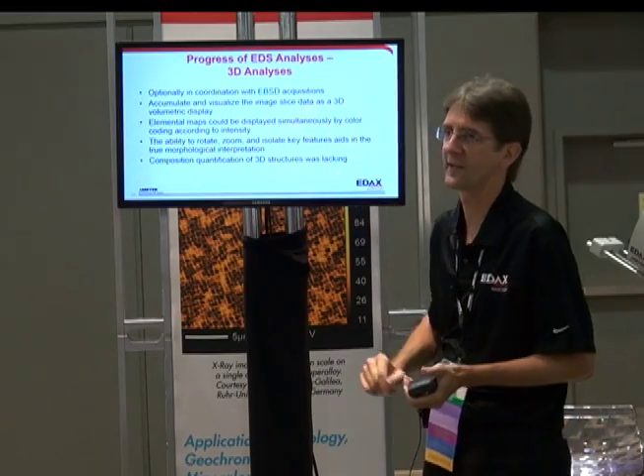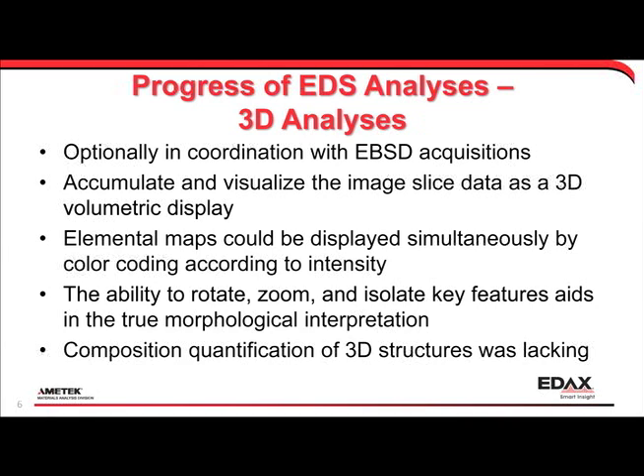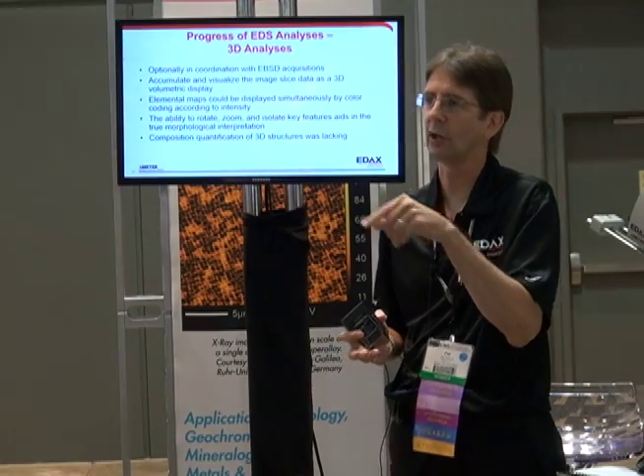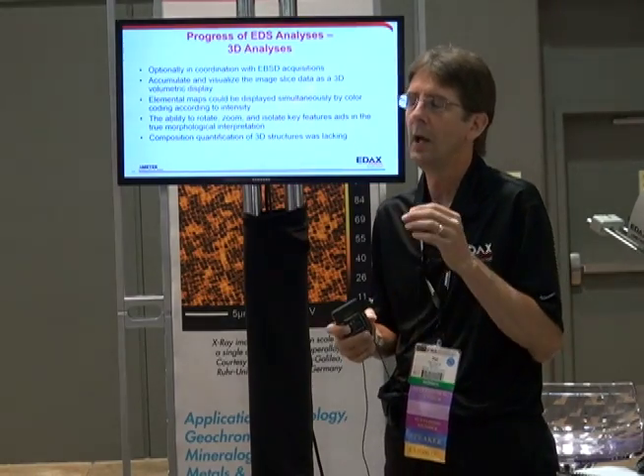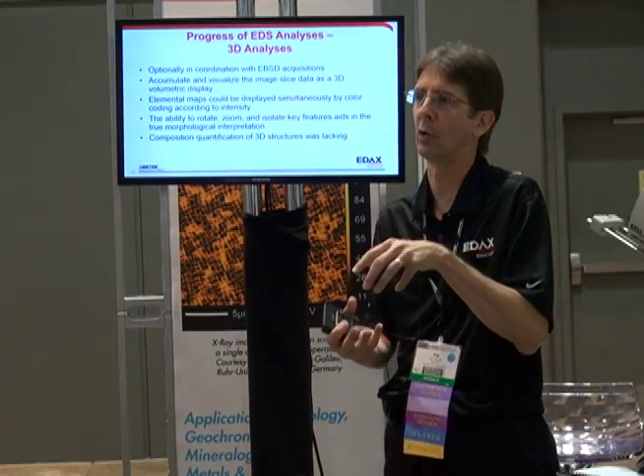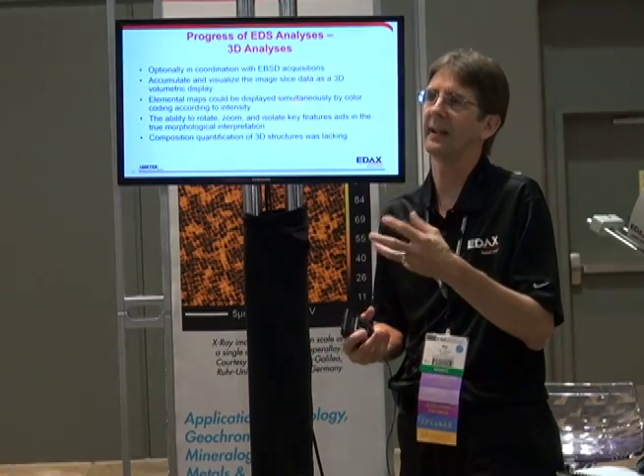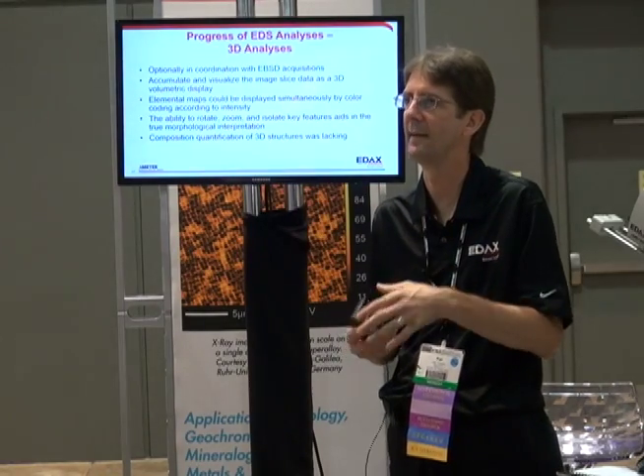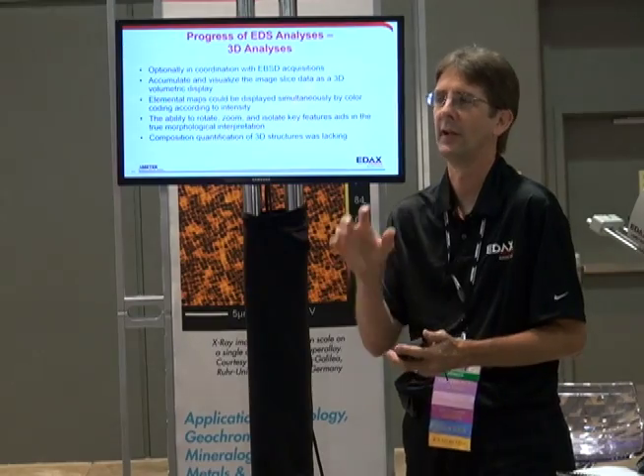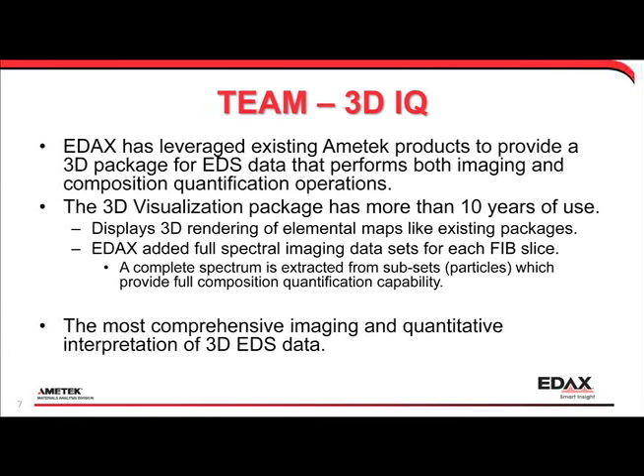The data is accumulated as a series of slices, and we want to take those slices and put them into a volume. Usually you'll do elemental maps — pre-selecting the elements, taking a series of section maps, and then you can rotate, zoom, and look through those. But as a microanalyst, what you really want is quantification — composition quantification. In the same way that you draw a line scan or circle a feature on a 2D spectral imaging dataset, you want to grab a volumetric particle or cuboid, extract a spectrum, and quantify individual particles within the data set in three dimensions.